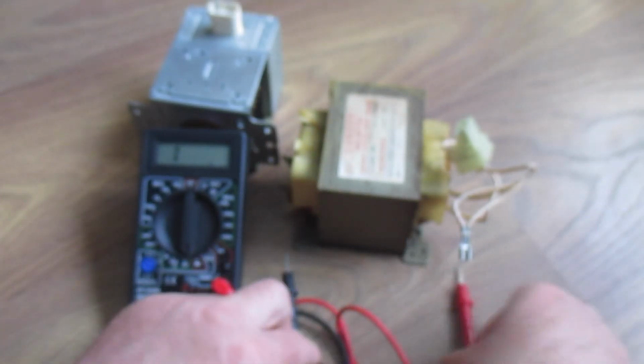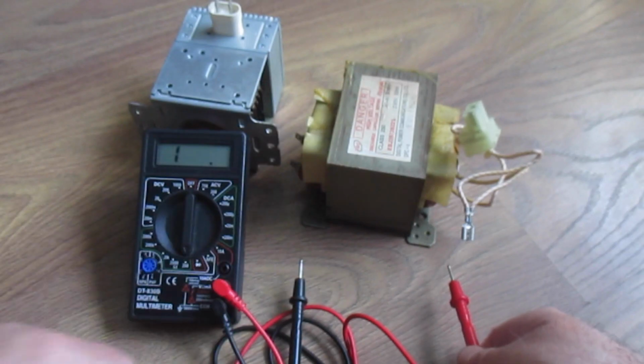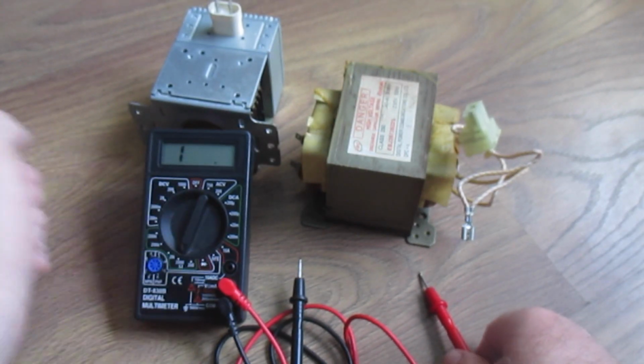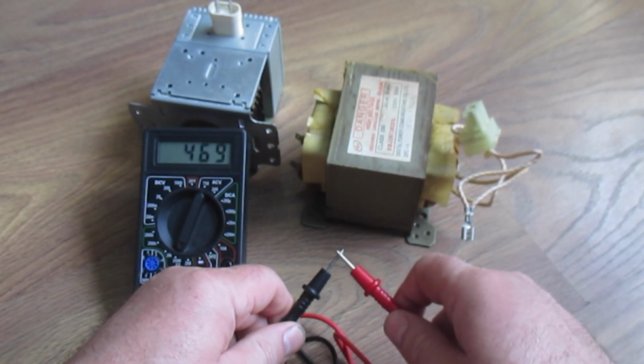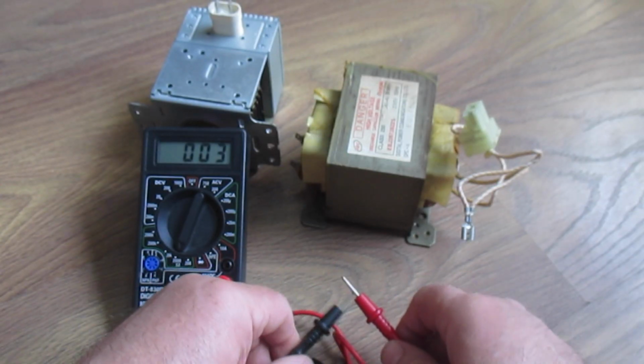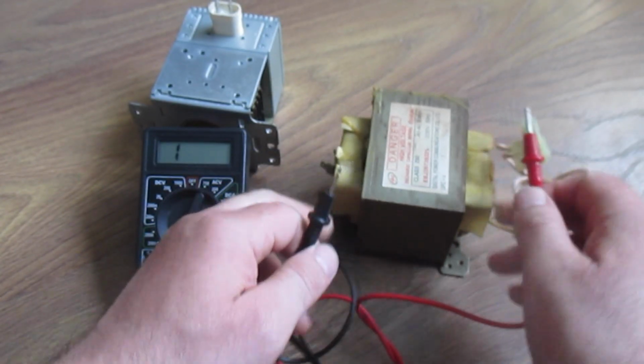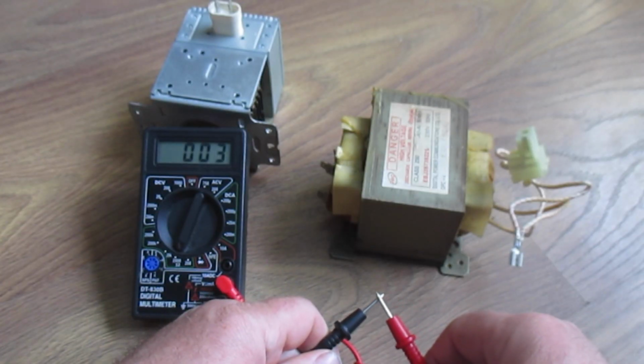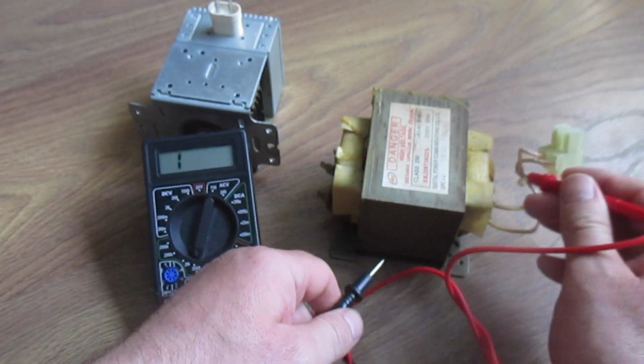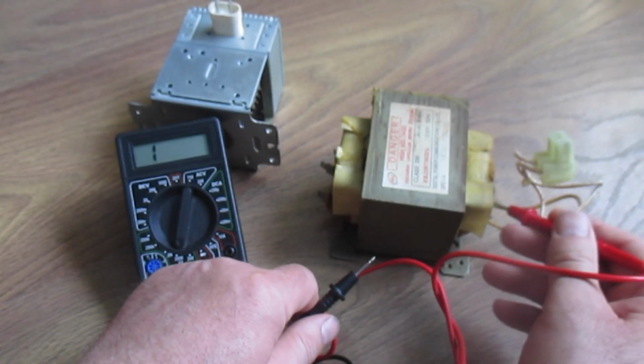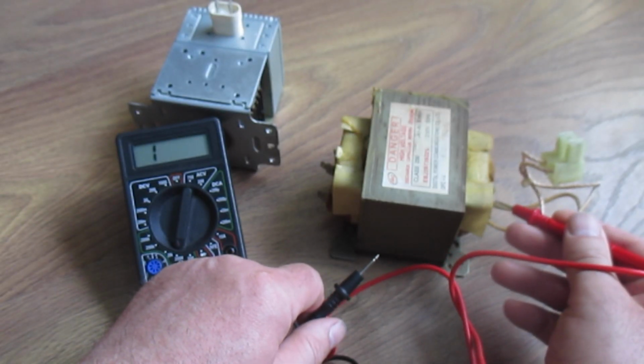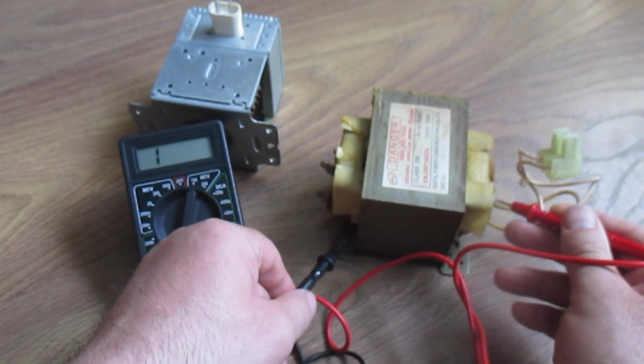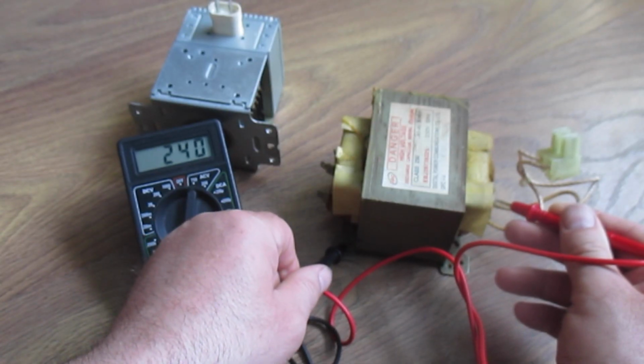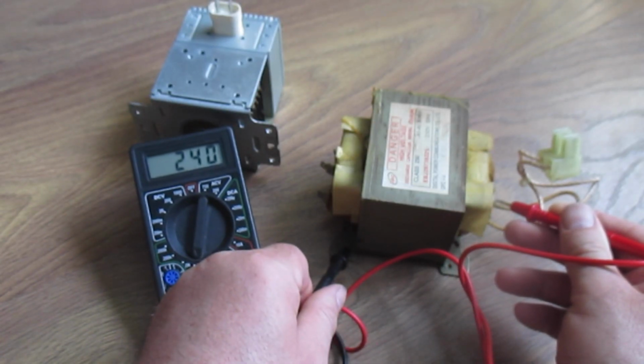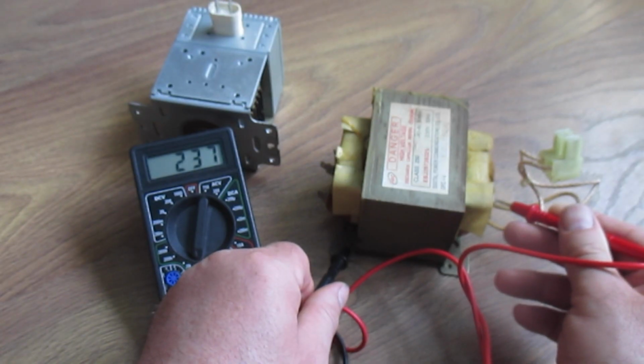Next, we check the secondary winding. To do this, set the multimeter switch to 2000 ohms resistance. Place the first probe on this contact and use the second probe to find ground on the case. The resistance shows 237 ohms, which is normal.